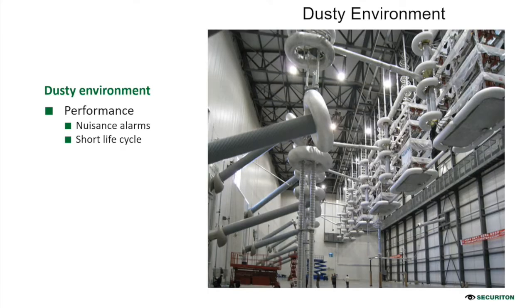Then the environment is not controlled, and sometimes dusty as well. So with normal detection, the chances of false alarms are always there. And the technology installed, other than aspirating smoke detectors, has a shorter lifetime. The exhaust fans are the main source of dust. High precision exhaust fans are the sources of the dust.